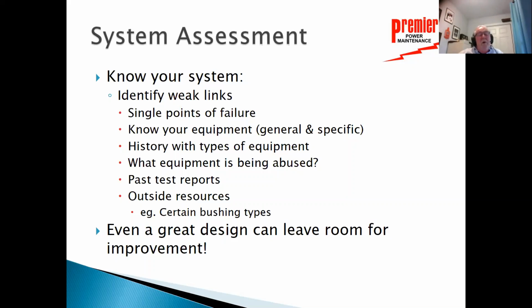We need to review ourselves with past test reports. Now, this is something that my company reviews quite closely. It's okay to do a test on a transformer, or a battery, or a cable or a circuit breaker. It's okay to come back for that test and say, you know what, all the tests we've done have met the criteria for all the standards that we deal with. That's great. But we need to also always look back at the past test reports.